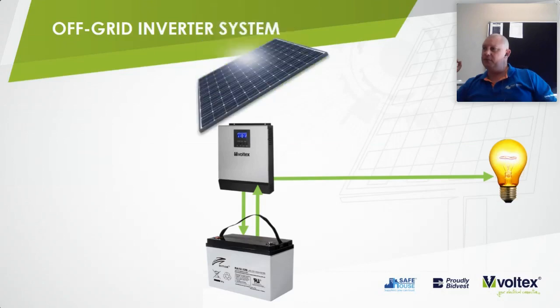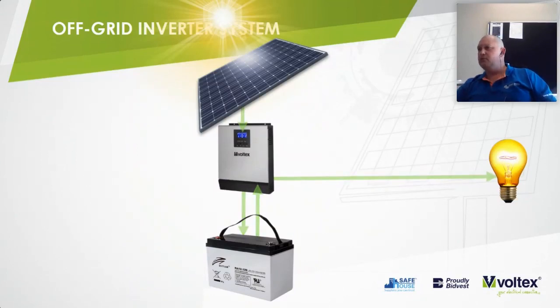But with this system, we add solar modules to the equation. As you do not have mains available, you need a source to charge your batteries in order to power your loads. So when the sun comes up, your system starts generating power from your PV modules, charging the battery and carrying your loads. When the sun sets, the inverter and battery setup takes over and carries your loads.